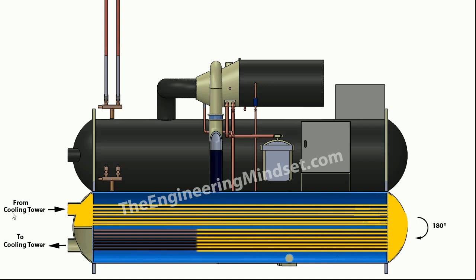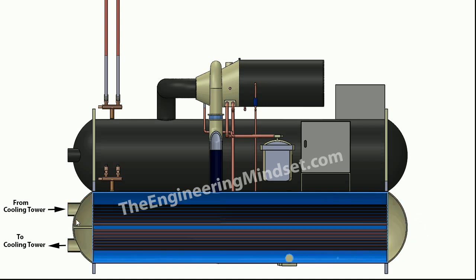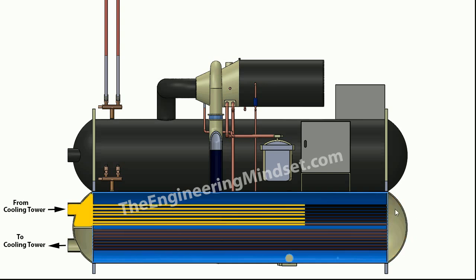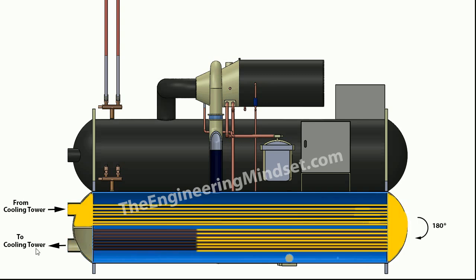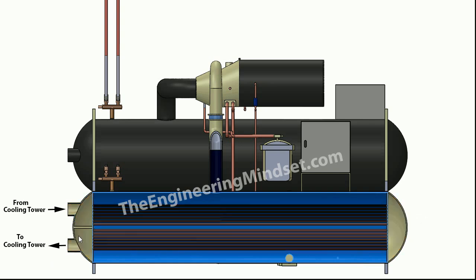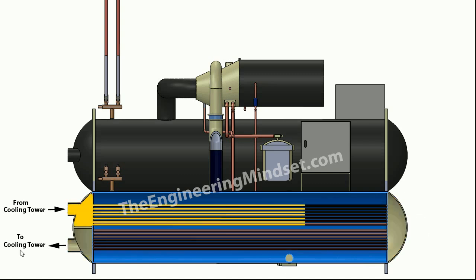The condenser water comes from the cooling tower into the condenser through the water box at the end — this section is removable. The water flows through the tubes all the way to the very end, hits the water box on the far end (which is also removable), does a 180-degree turn, comes back through the tubes, and then exits out of the water box off to the cooling tower, taking any heat it has picked up with it. There is a baffle in between the two flows just to separate and divert the flow through one side.